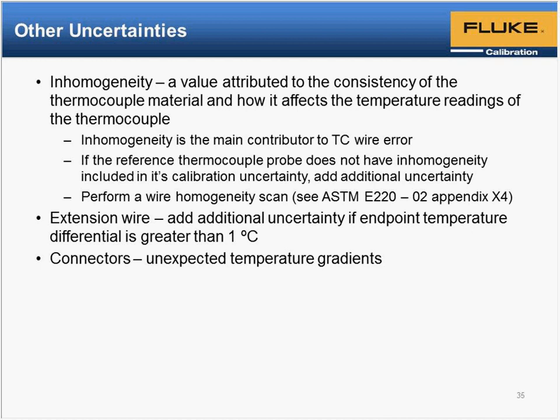In another webinar, we'll talk about thermocouple principles. We have some suggestions on how to measure thermocouple inhomogeneity. With extension wire, you have to consider the environment. If the room that you're measuring in has a 1°C difference between the endpoints of the wire, then you need to add additional uncertainty.